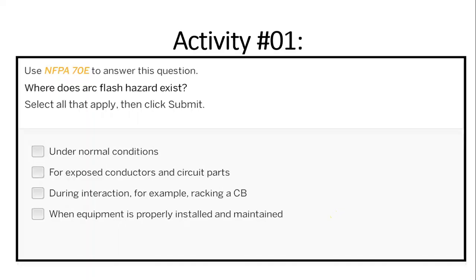So if anyone can answer this one. Number 2. Number 2 is fine. Number 2 and number 3. Why not number 1? Under normal condition. Normal condition is defined by NFPA 70, the National Electrical Code. In normal condition, when you are not interacting with the electrical equipment, it is believed that an arc flash hazard should not be there, because it is controlled by the design of the equipment, the installation procedure and other things, and the maintenance is proper. So number 1 is not the case.